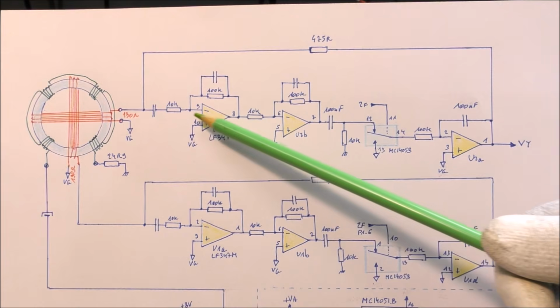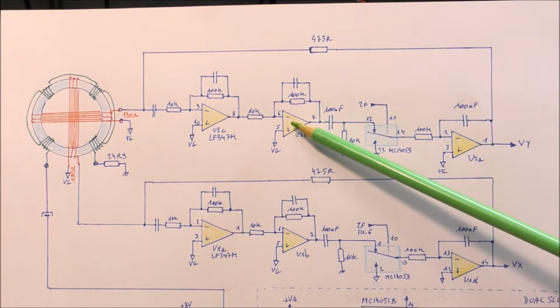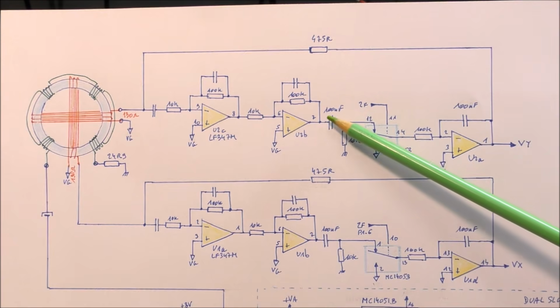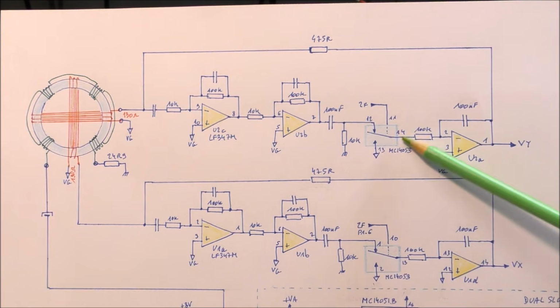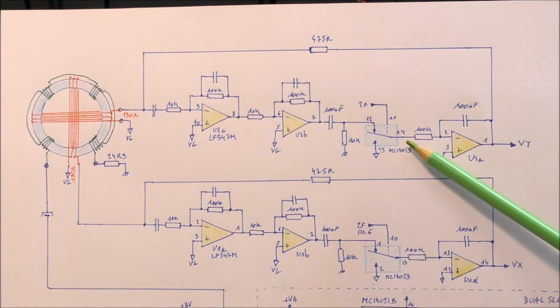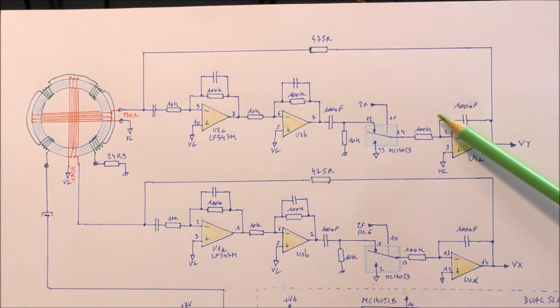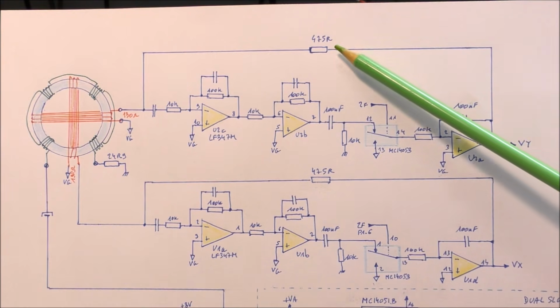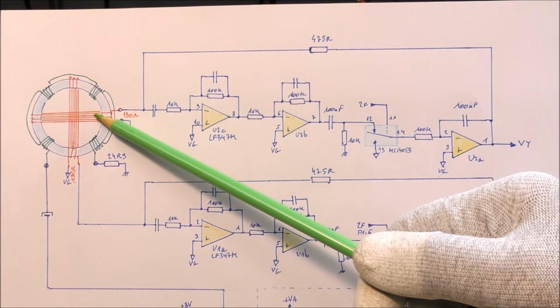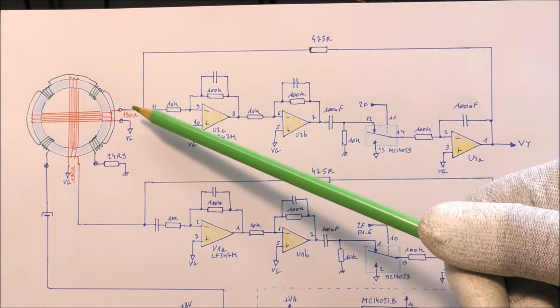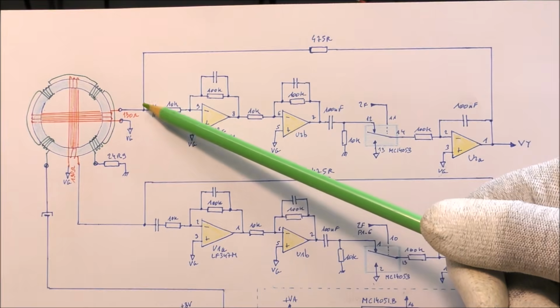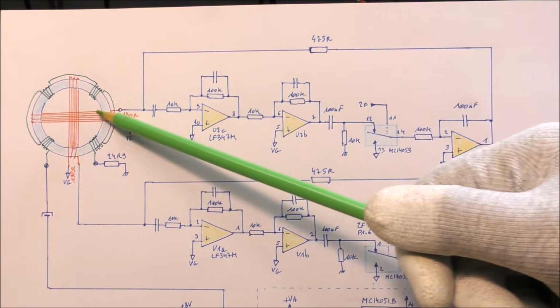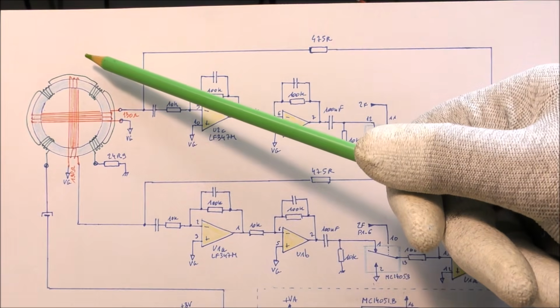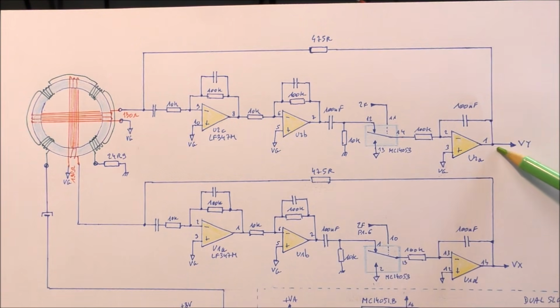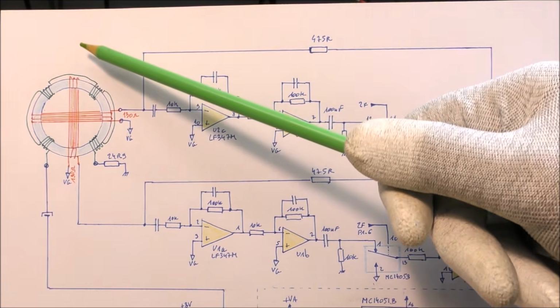This error signal is amplified. You can see that we have 2 amplifiers in cascade. The gain is 100, and this signal is fed to this phase detector. At the output, there is a DC component. This DC component is fed to this integrator. The voltage at the output of this integrator is converted into a current using this feedback resistance, and this current will generate a magnetic field. At the end, when the second harmonic here disappears, the magnetic field generated by the coil here is identical to the external magnetic field. Therefore, the output voltage here is an image of the magnetic field.